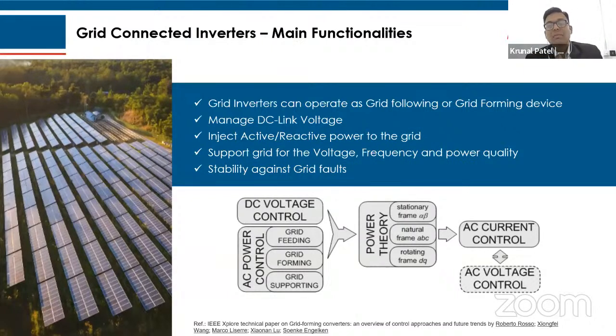So now this is also very important with respect to the various grid codes as well as the microgrid grid codes. Stability with respect to faults, like LVRT, low voltage ride-through, and high voltage ride-through faults. This should be the characteristic to be defined and adjusted in the case of grid-connected inverters.